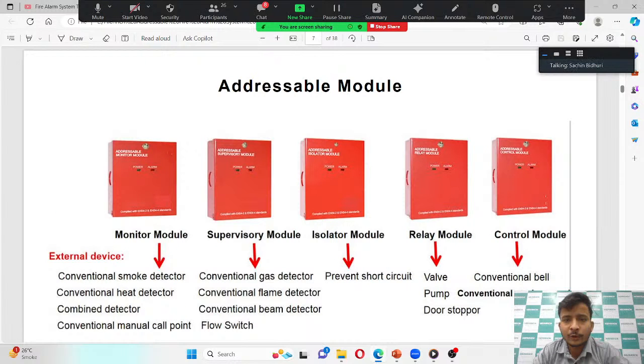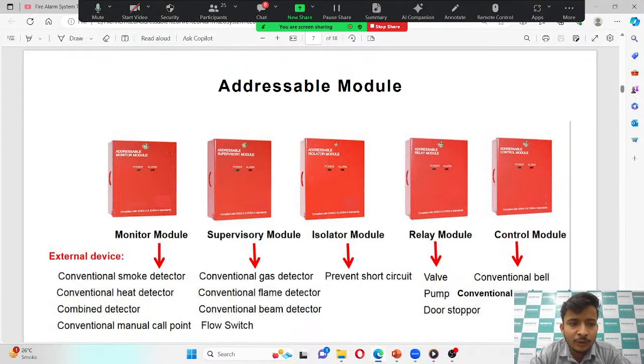Then we have different types of modules, as my colleague Sachin already told you about the modules. Monitor module: what is the application of the monitor module? It can be used for adding conventional devices to the same addressable fire alarm panel or fire alarm system. You can add conventional detectors and conventional MCPs with the help of this monitor module. Then we have the supervisory module for adding gas detectors, flame detectors, beam detectors, all the conventional ones.